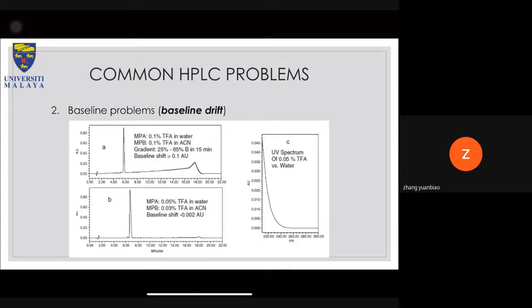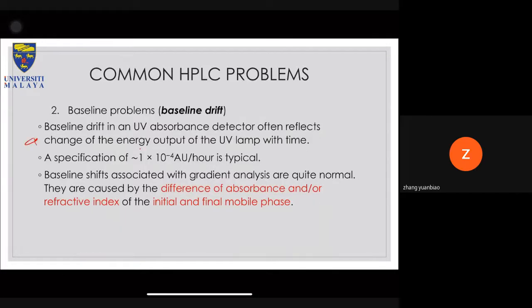Baseline drift in a UV absorbance detector often reflects a change in energy output of the UV lamp with time. A specification of about 1 times 10 to the minus 4 AU per hour is typical. Baseline shifts associated with gradient analysis are also quite normal. So this is the one that I mentioned in the previous slides. They are caused by the difference in absorbance and or refractive index of the initial and the final mobile phase.